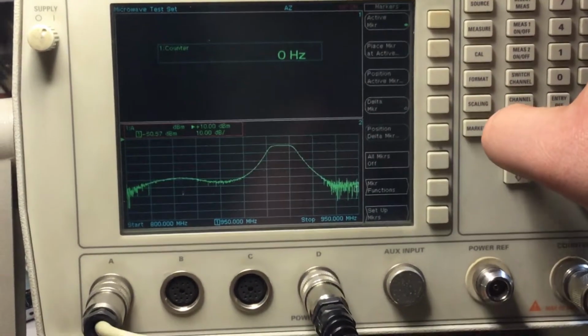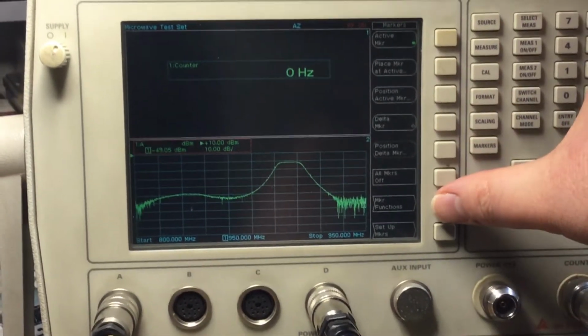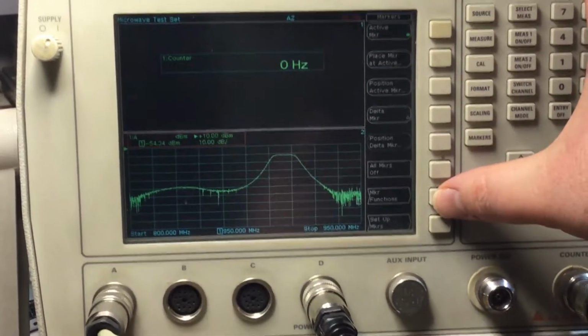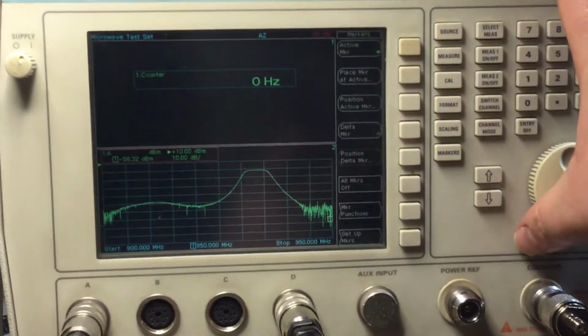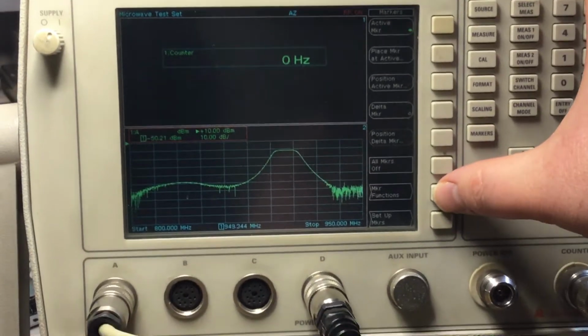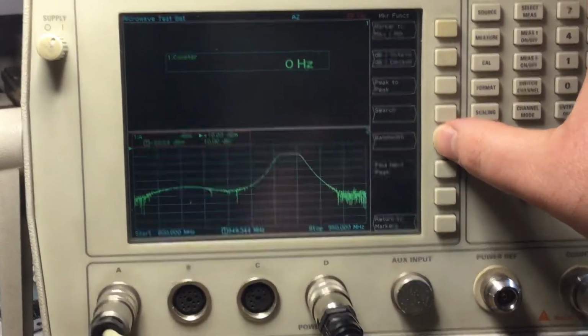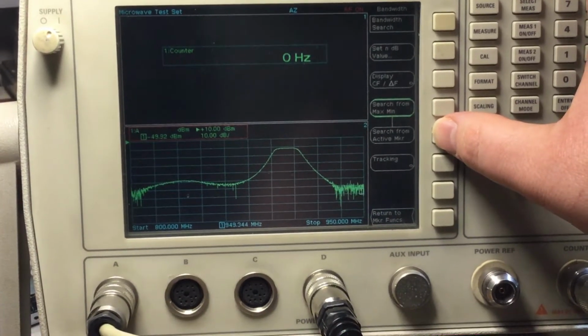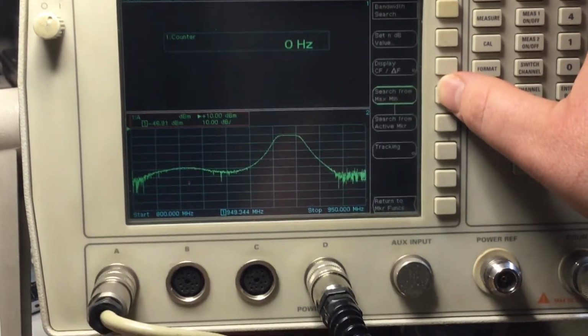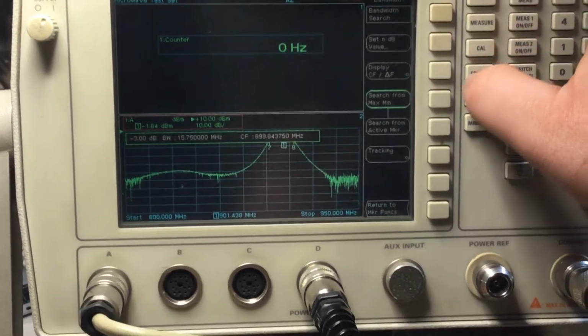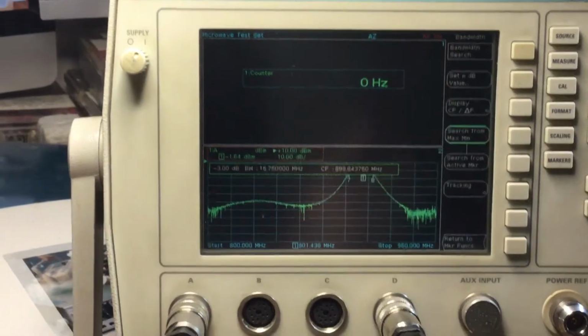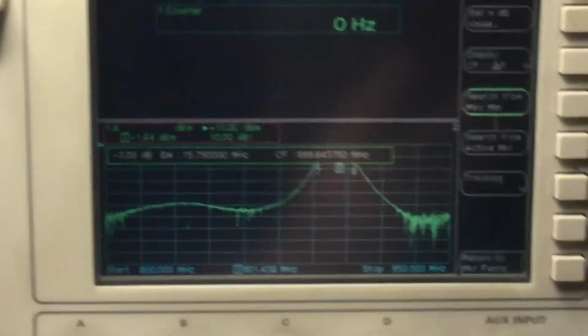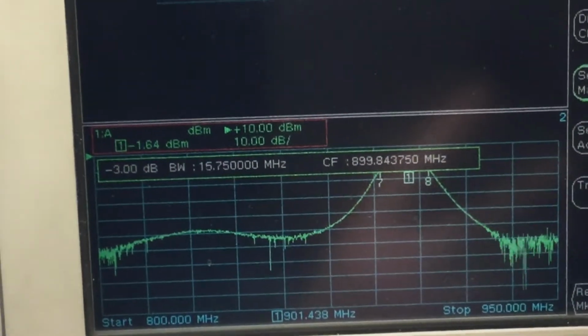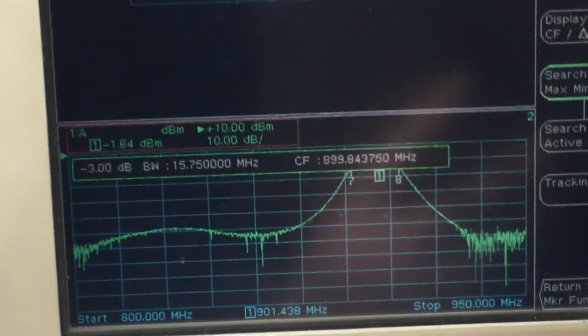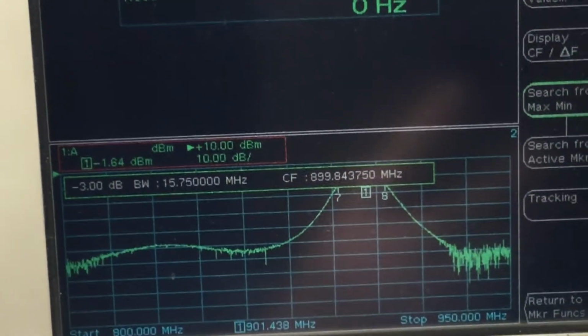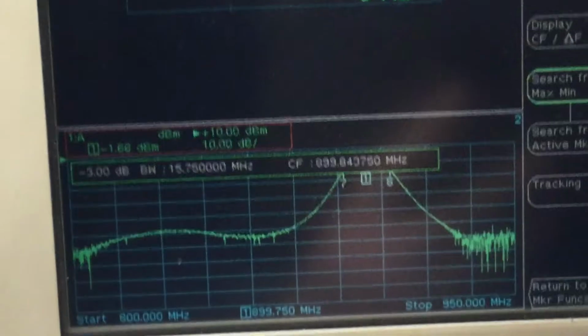And then of course we've got markers. Now the nice thing about marker functions as well, which I'll get to, is that you can actually set up bandwidth measurements, and it'll give you the bandwidth of the filter. So we can set up marker functions and then do bandwidth, and then we can do search from maximum to minimum. We can do a bandwidth search, and now it'll give us the details as to the bandwidth of the filter automatically, which is quite nice. So we can see the 3 dB points, what the bandwidth is, and the center frequency, and we can also move a marker as well if we want to with the rotary control.